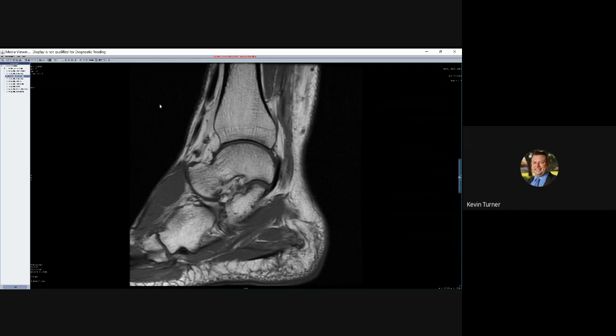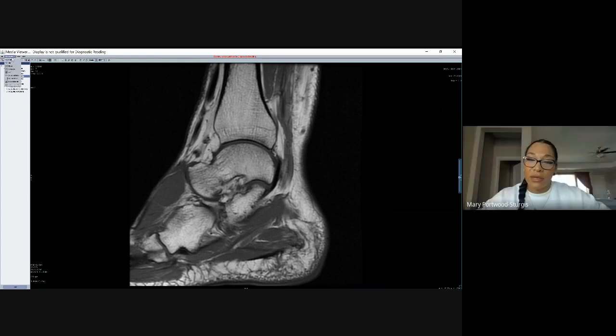It is, but here you can't. Here you have anatomy outside the field of view that's inside the coil, in both directions. Okay. So you kind of get stuck here where you've got to then figure out what's going to happen. And in reality, the coil only goes so far up on the foot here. Another thing you could do is just make your field of view bigger so that it included all the anatomy in the coil up here and then make that your phase direction, and then you wouldn't get wrap in your frequency.